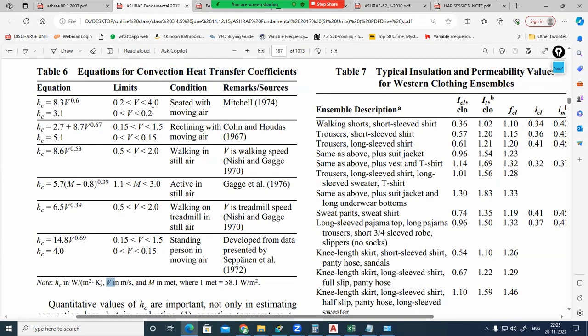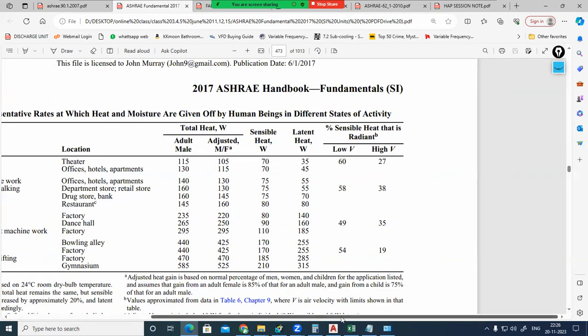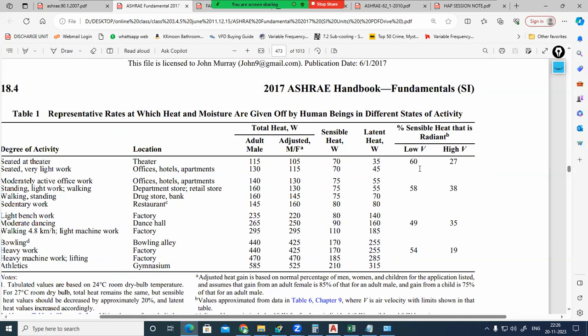With respect to the velocity variation, the rate of heat ejecting from the body varies: seated with moving air, reclining with moving air, walking in still air, active in still air. So with respect to the velocity of air on the human body, the amount of heat ejected to the surroundings will vary. But we don't want to spend that much time on in-depth detail. So from this table only they found that value. Anyhow, we can go to that Table 4.7.3 of this same handbook. Sensible percentage of sensible heat gain: 60 percent. If the velocity is more, it will decrease to 27.